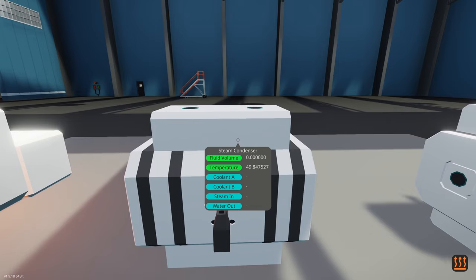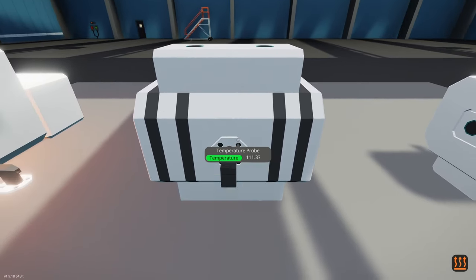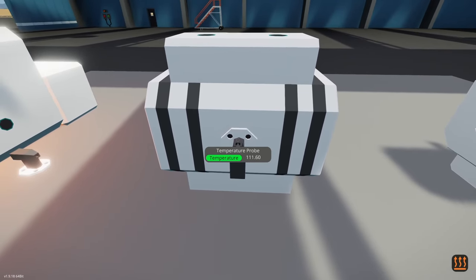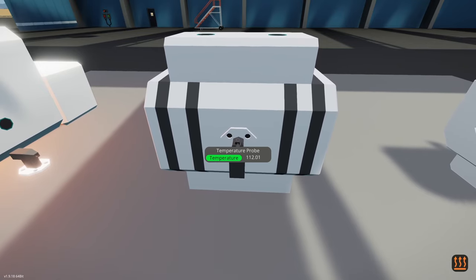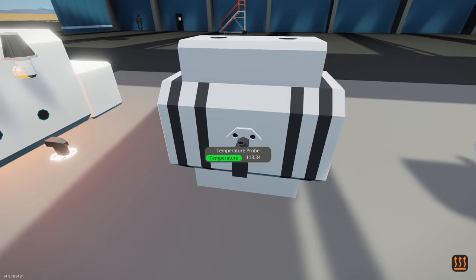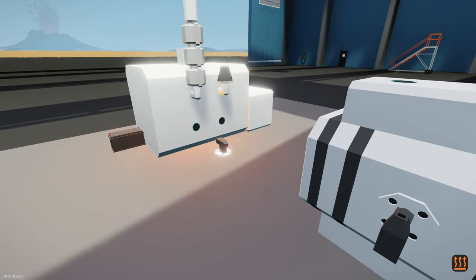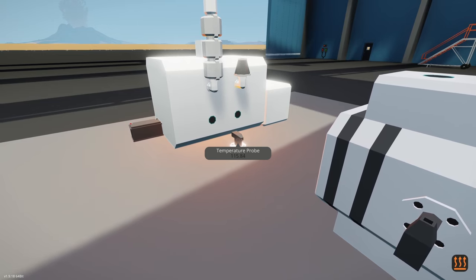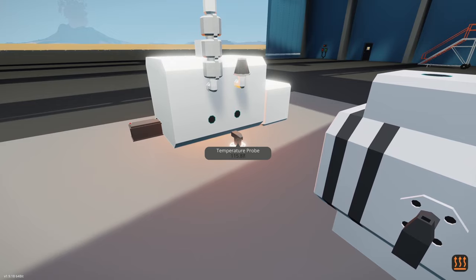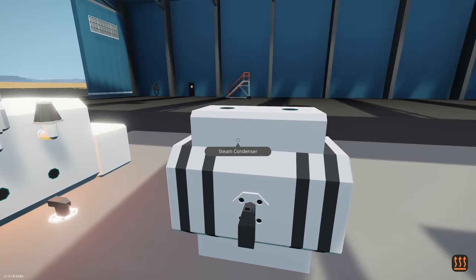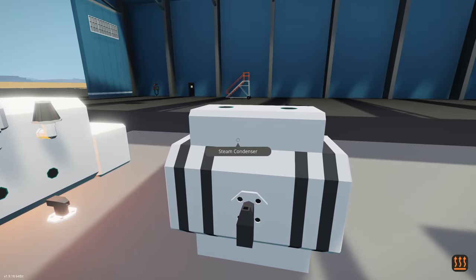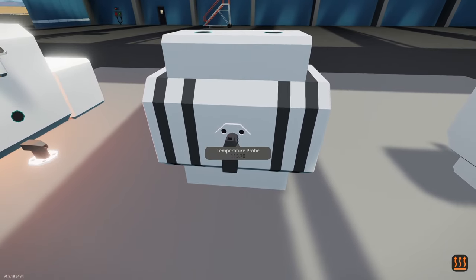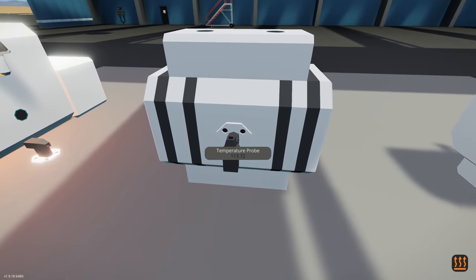Notice the temperature of the condenser — it's going up. The probe right here is at 111 degrees. If we look at another probe, we're at 113 degrees at this condenser; 115 degrees at the next. Anything over 100 degrees is going to cause water to boil and create steam. The whole point of the condenser is to cool the steam to turn it back into water. So if our temperature is over 100, we're defeating the purpose of this.